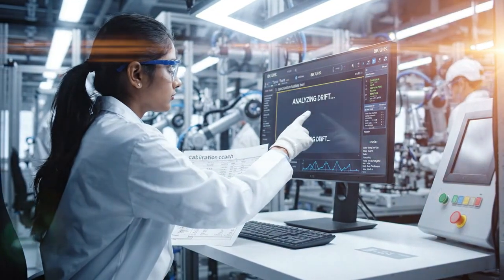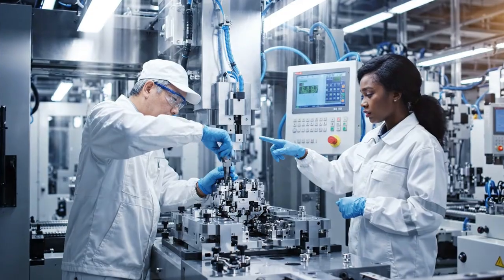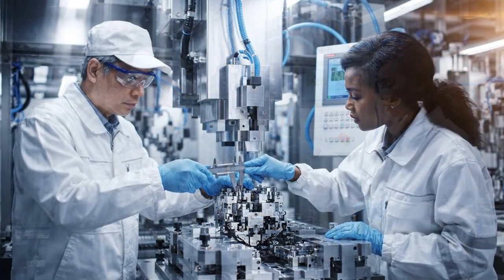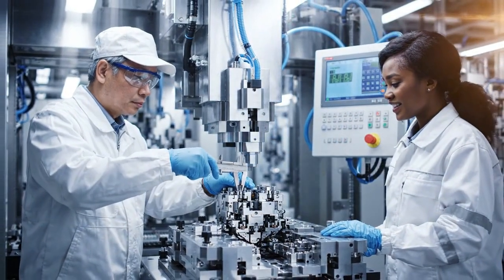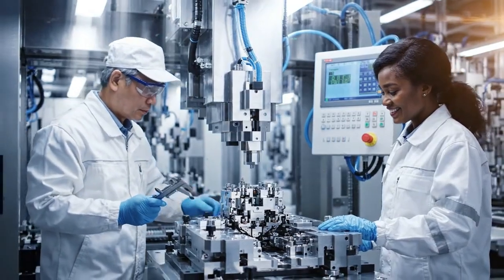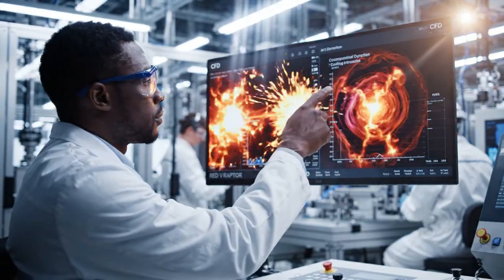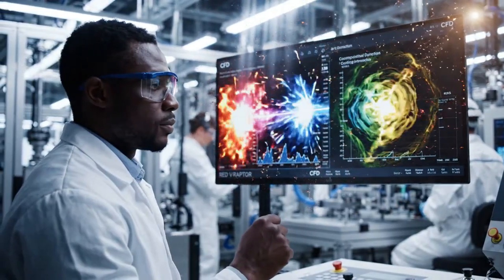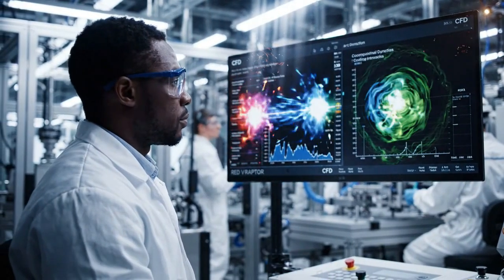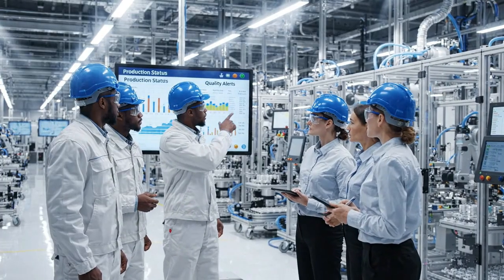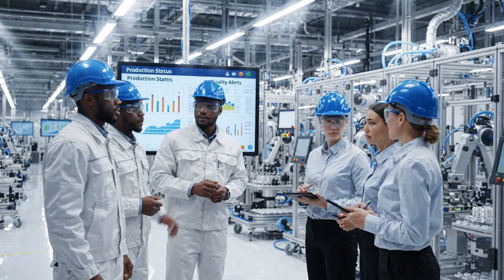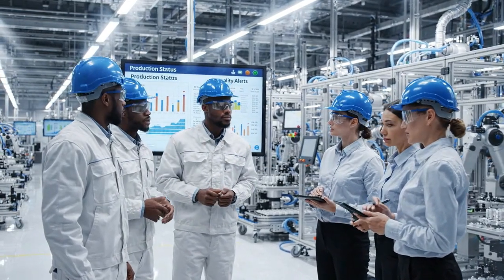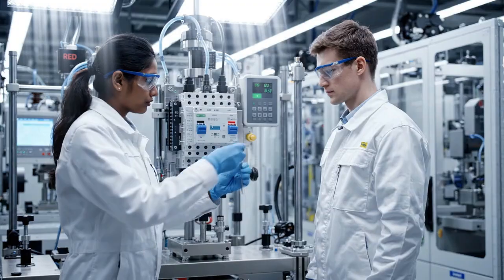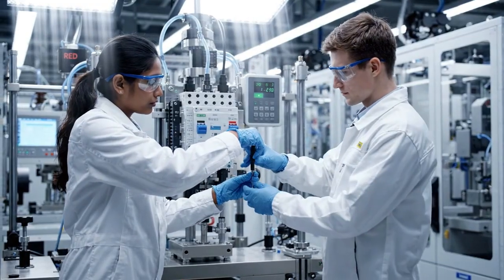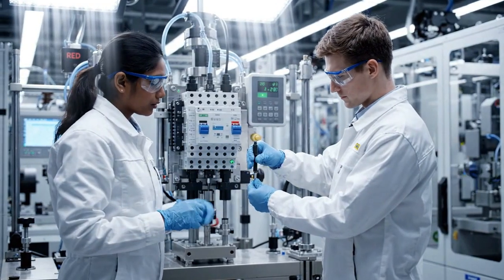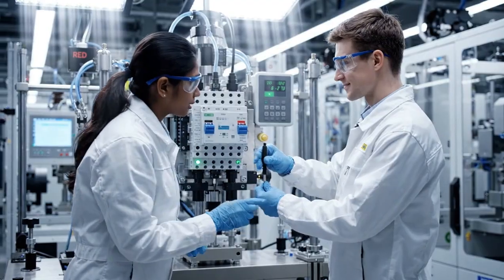Die maintenance ensures consistent component quality. A worn stamping die produces parts with dimensional variation that affects breaker calibration accuracy. Arc simulation models the extreme physics of circuit interruption. Temperatures exceeding 20,000 degrees, pressures exceeding 10 atmospheres, all in a few milliseconds. Calibration training takes months of supervised practice. The technician must develop the sensitivity to achieve exact trip current specification on every breaker.